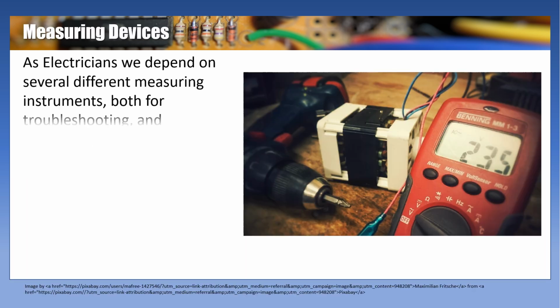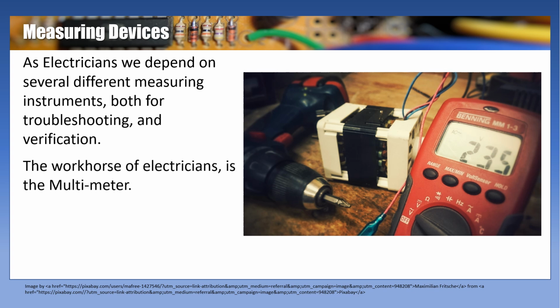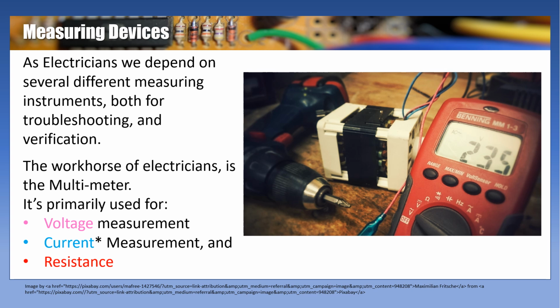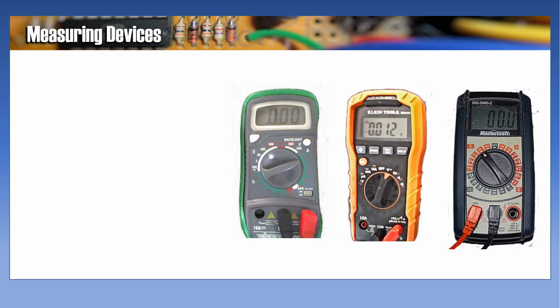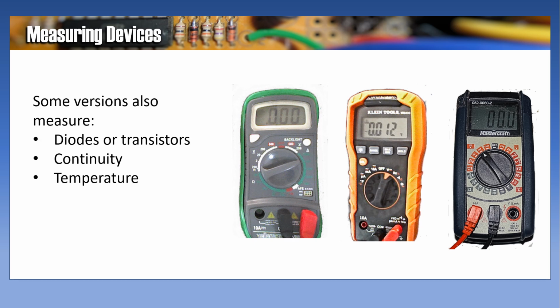As electricians, we depend on several different measuring instruments, both for troubleshooting and verification. The workhorse of electricians is the multimeter. It's primarily used for voltage measurement, current measurement, and resistance. Depending on the manufacturer and the meter itself, some versions also measure diodes or transistors, continuity, temperature, and capacitance.